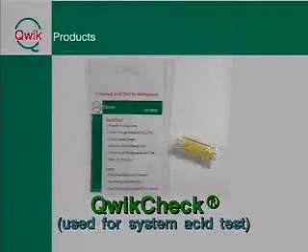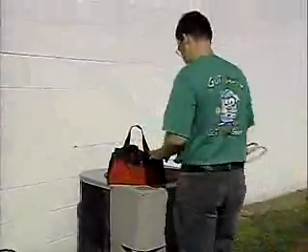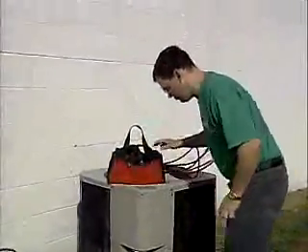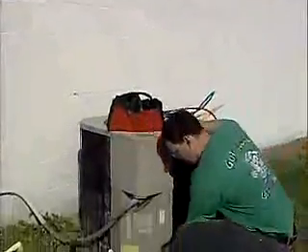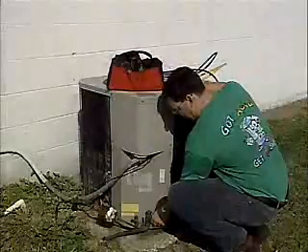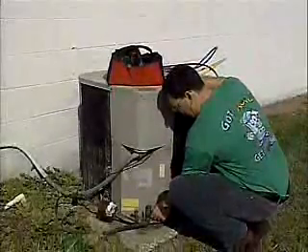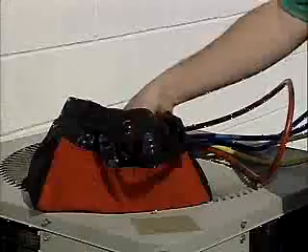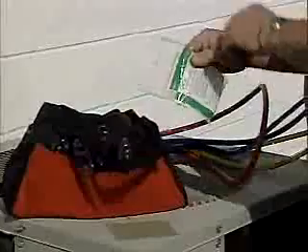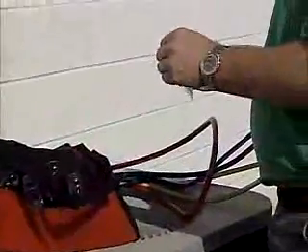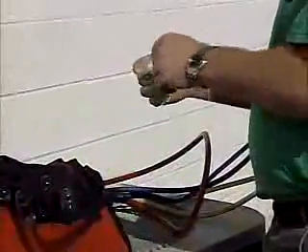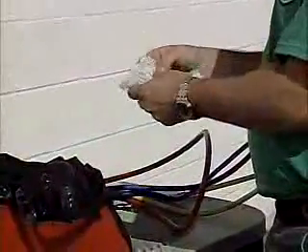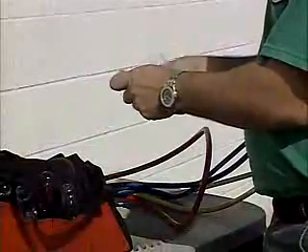QwikCheck tests for acid in a system in just five to ten seconds. To perform an acid test, simply hold QwikCheck against the low-side Schrader valve of an operating system. This method allows the technician to perform an acid test without removing oil, which is a key feature making testing a typical hermetic system simple and easy.